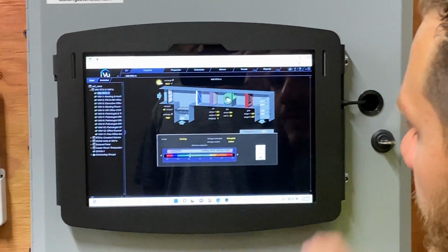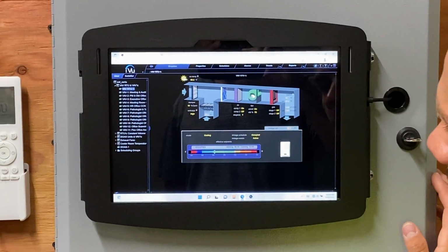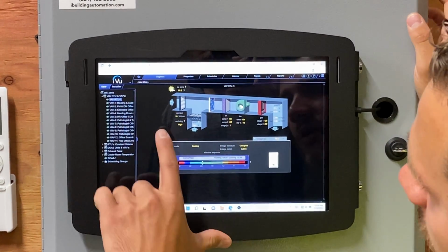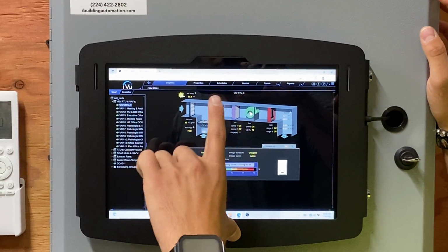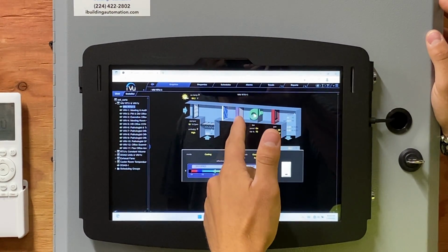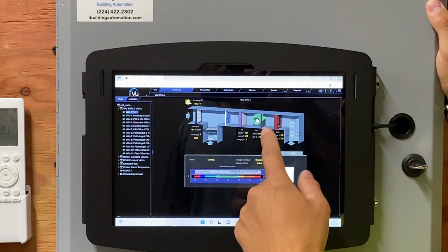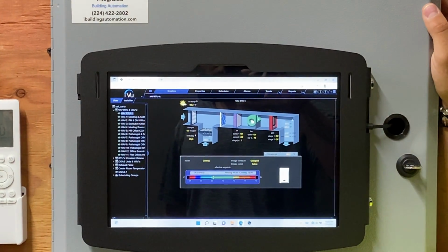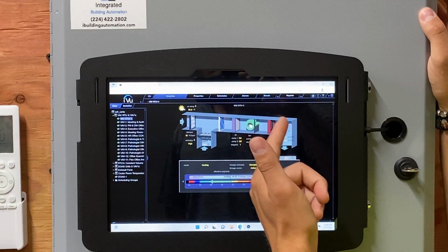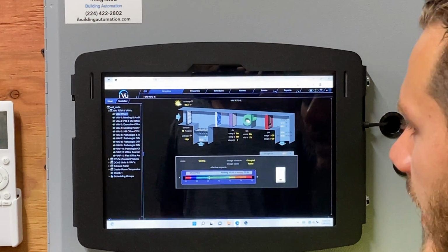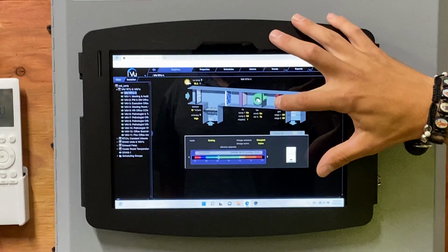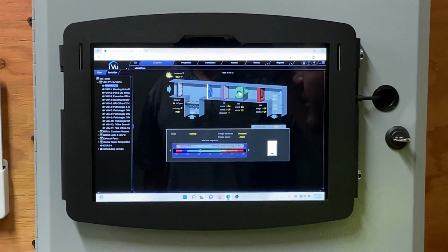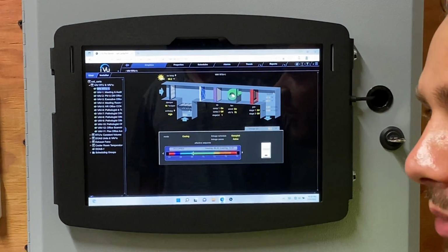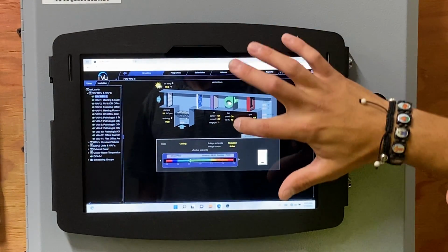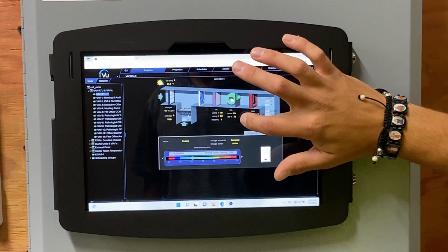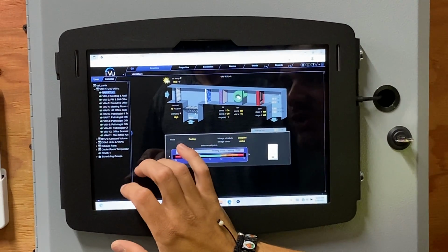Again, at the rooftop here, we can start from one side of the rooftop all the way to the other. You have your outside air damper here. This is your return air, which comes up, shows a filter, our DX mechanical cooling, our blower motor, and as you can see, the blower is spinning, our gas heating, and then our leaving side. A couple of important values we're going to want to look at here: number one, we always want to make sure we have fan on, because if we do not have fan on, the unit's not going to operate for either heating or cooling. Okay, so we have fan on. It's showing 73% right now.